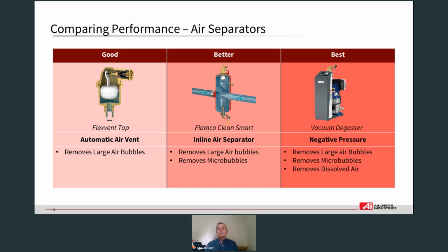What we utilize is vacuum degassing. It treats the water from the system in certain specified amounts. The water is subjected to reduced pressure, releasing all the dissolved gases, and the degassed water is returned back to the system where it absorbs further air it meets in the pipework. That saturated water is fed back to the degasser and once again subjected to a vacuum to remove the dissolved gases. So it's really impossible to predict where air will be released in a system, and therefore an important reason for choosing a vacuum degasser over an inline deaerator, which we also supply.